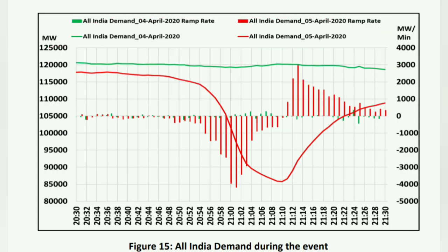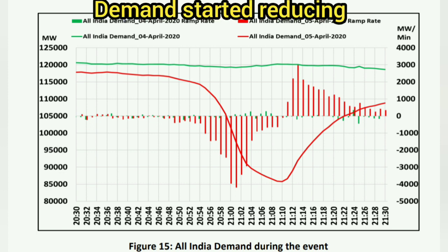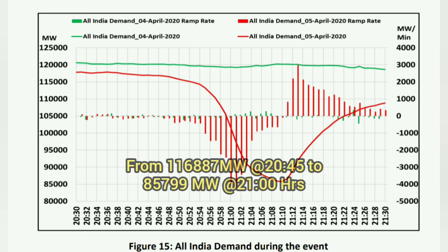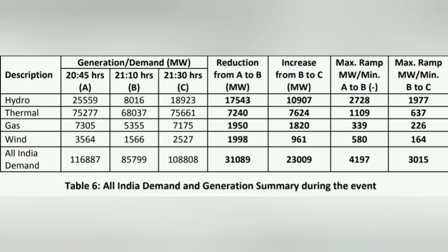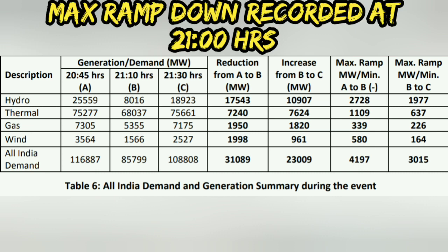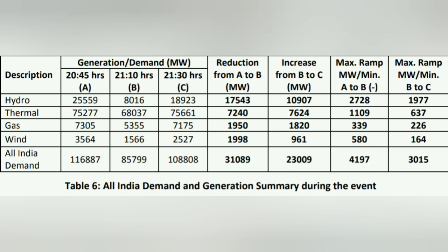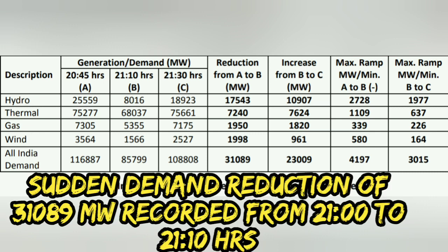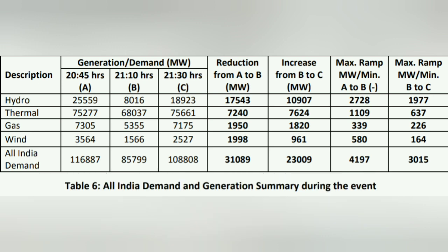The all India demand started reducing sharply from 1,16,887 megawatt at 8:45 p.m. and touched the minimum value of 85,799 megawatt at 9 p.m. The maximum ramp down was recorded at 9 hours. This sudden fall in demand of 31,089 megawatt was managed effectively with matching generation backed down in hydro, thermal, gas and wind generators across the country.